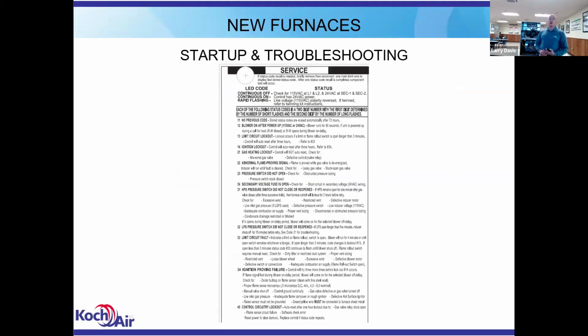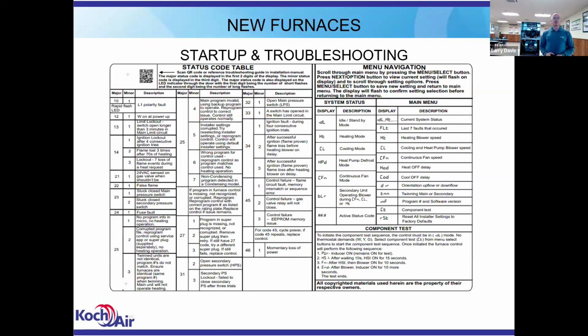Fault codes. This is something that you've seen in our previous model furnaces. This is our fault chart. It lists the particular faults, and under some of the faults, you may have several different options of things that could be going on. With these new boards, we get more information. So this is an example of the fault code table that you'll see in the new furnace. And you can see, for example, on the fault code 14, I now have a 14 with a submenu, a subcode of 1, 2, or 3.